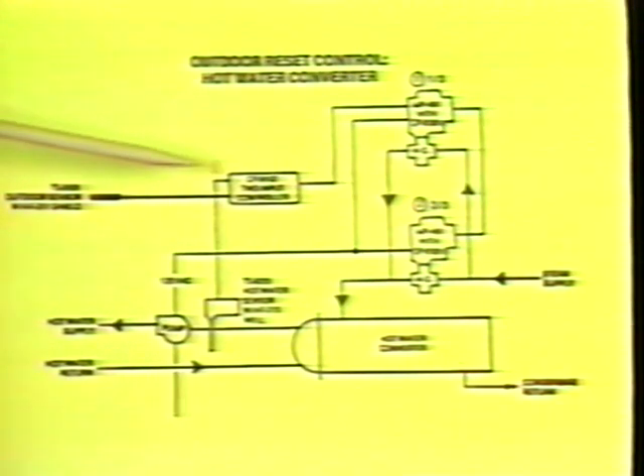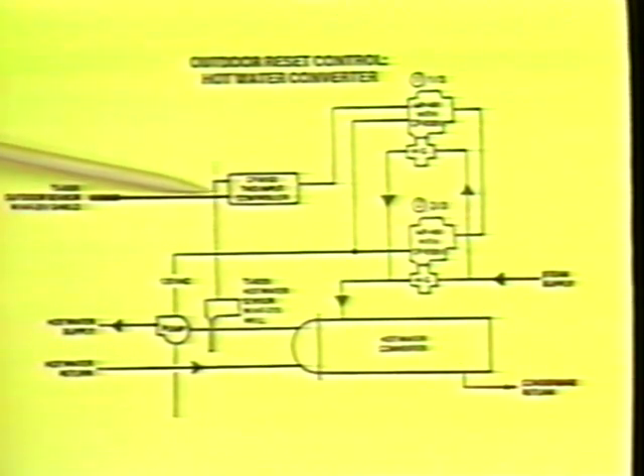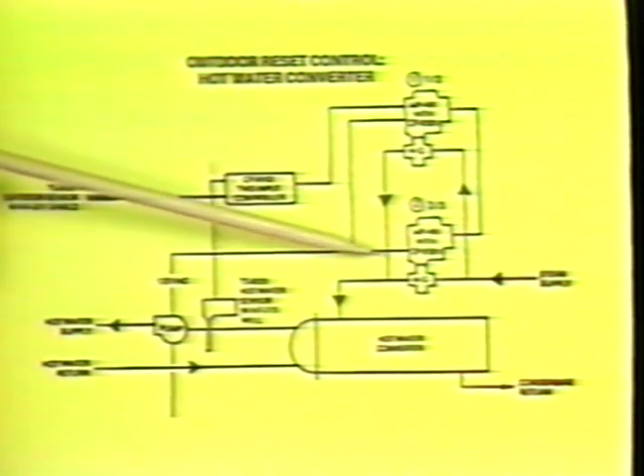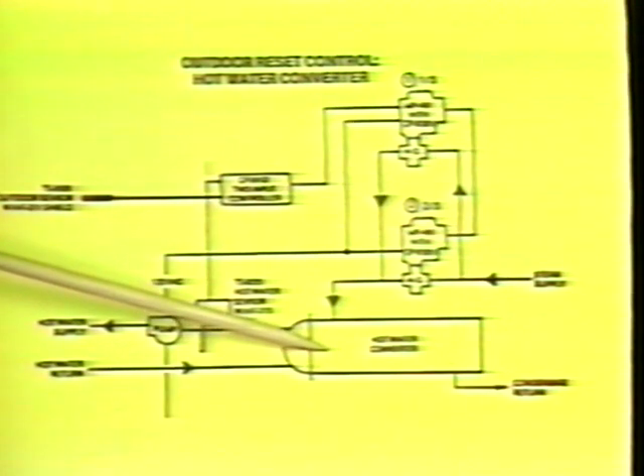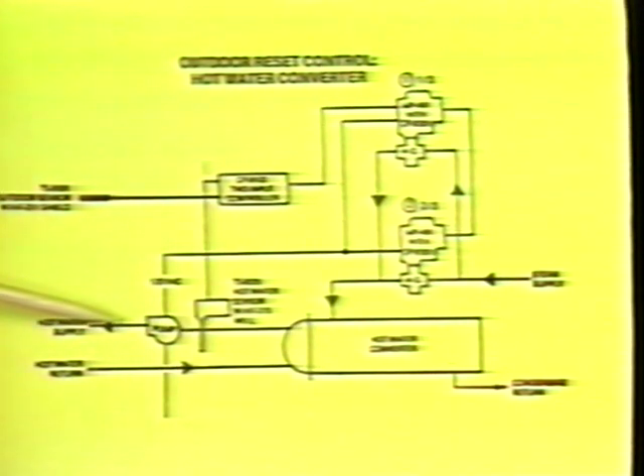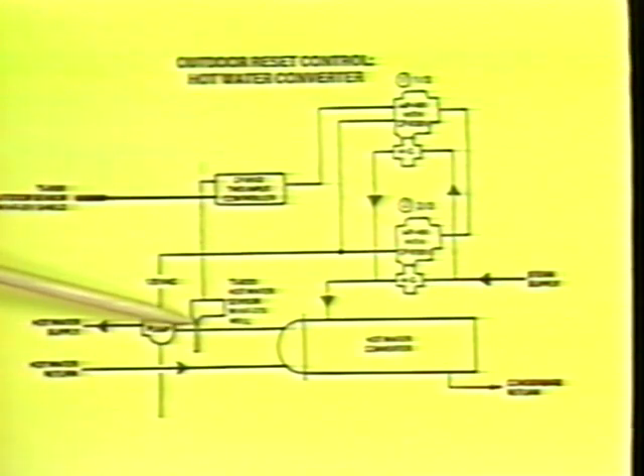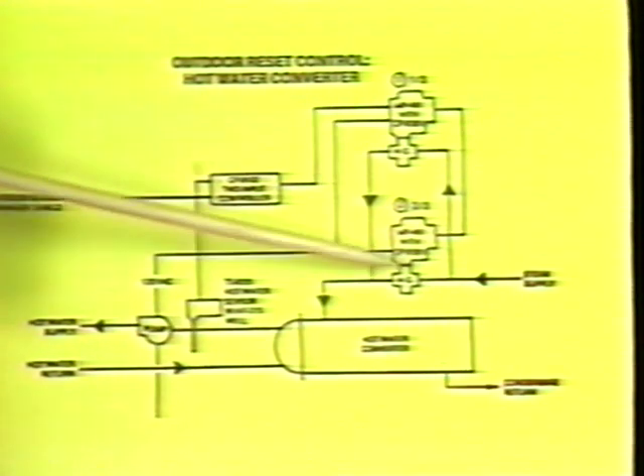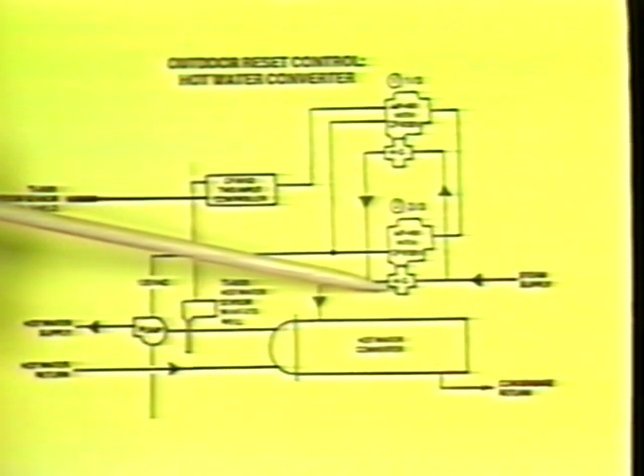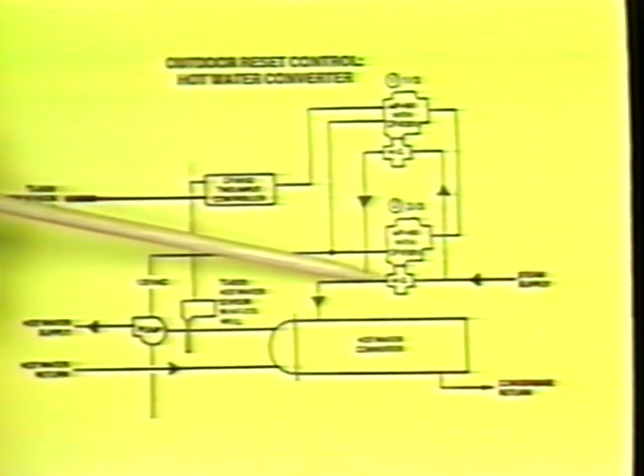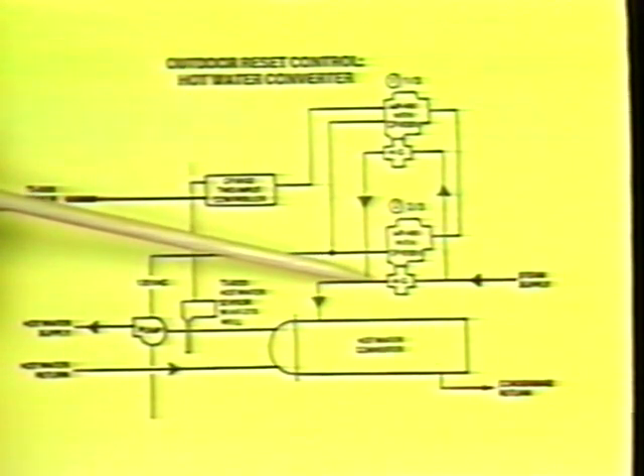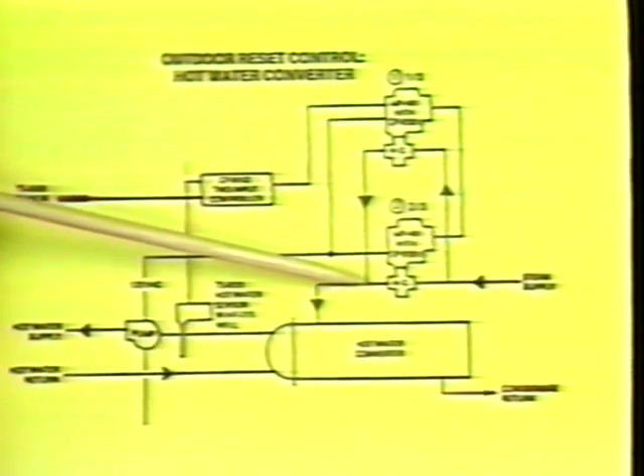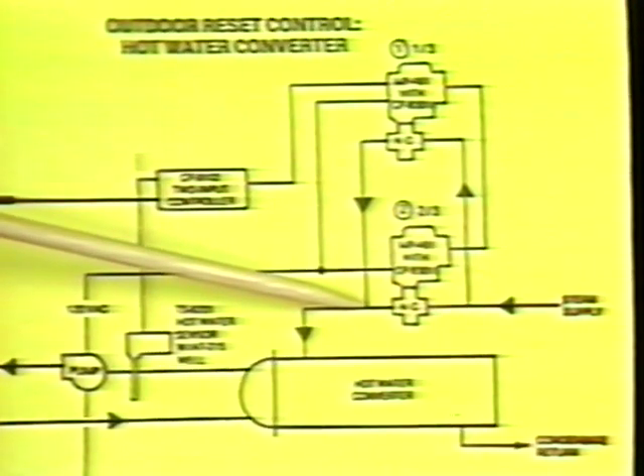Here's another example. This time our 2-input controller is controlling 2 steam supply valves providing steam inlet to a hot water converter. The output of the converter is the hot water we're going to use for some purpose. The controller is sensing that hot water output temperature. Both of these valves are normally closed. That means as the hot water temperature rises, we want to allow those valves to go toward closure. A falling controller signal will allow us to do that. This time, as the temperature rises, we want our signal to drop. Therefore, a reverse acting controller is required.